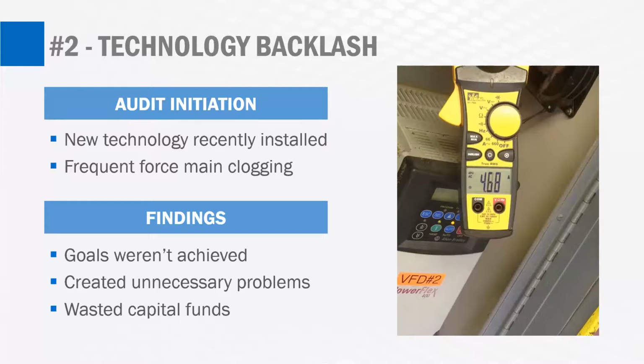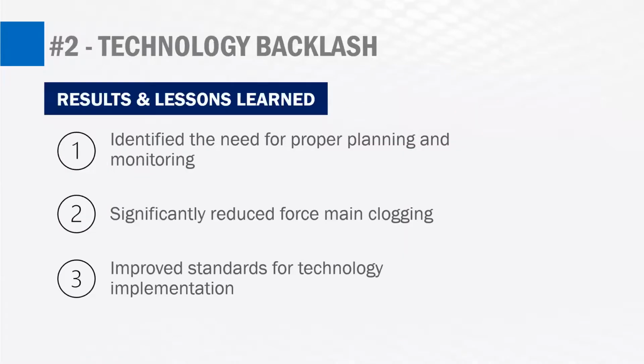Luckily, in this case, a lot of the clogging was able to be relieved by increasing the pumping rate more frequently than once or twice a day to get the scour velocity up in the force main and help it self-clean. But there were some instances where pigging needed to be done to clean out the force mains completely. And overall, there were capital funds wasted in this program that were not able to be recouped due to the lost electrical efficiency. Next slide.